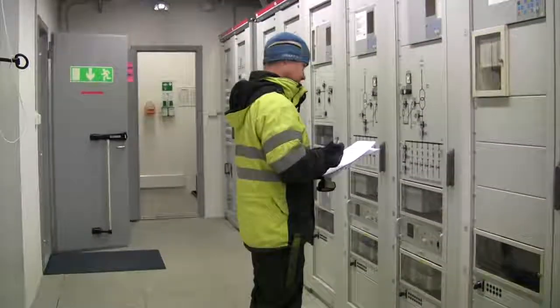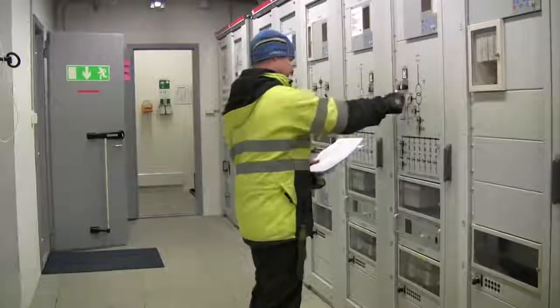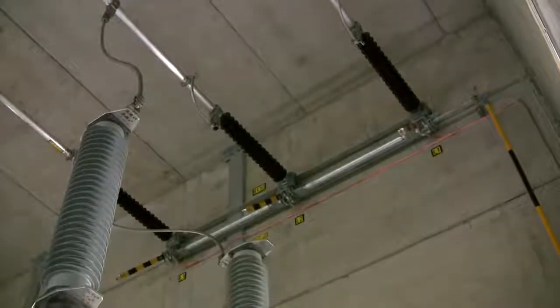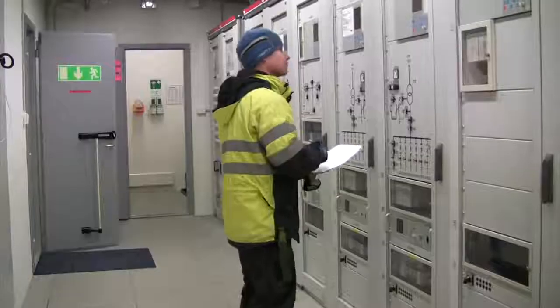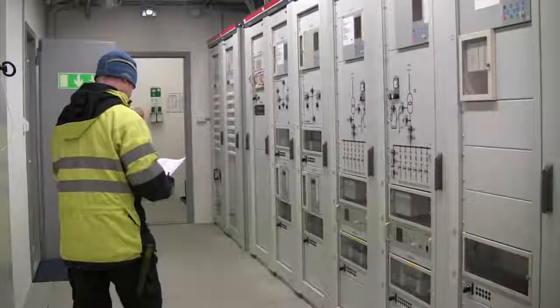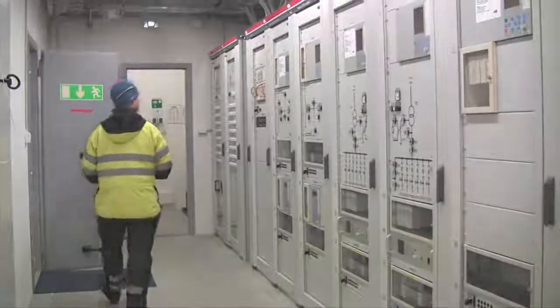The motor-operated grounding switch on the bus bar is opened first. Next, the disconnecting circuit breakers are unlocked. They can now be closed to put the bus bar and transformer back in service.